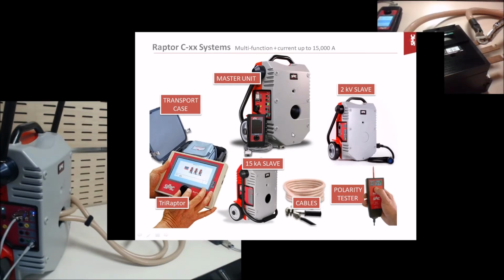And there are a number of options and accessories that you can complement your Raptor system with. For example, a high voltage converter if you need to test anything up to 2 kilovolts. Or high current amplifiers, which we call slave units. Each of these amplifiers adds 5 kilovolt ampere power to the system. So when you have a long impedance, so you need very, very long cables to connect to the element that you are testing, whichever it is. It might be a circuit breaker, a bus bar, a transformer, or whatever. When you need long cables, you will possibly need an additional current amplifying unit like this one here.